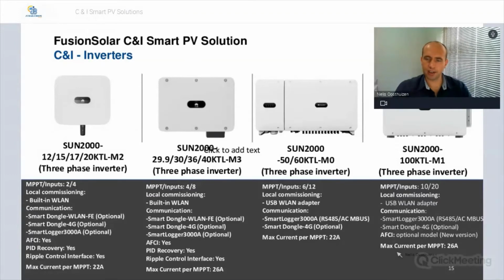And then note again that the maximum current per MPPT is 26 amps, which means it supports all the newer high-powered modules, which have a short-circuit current of about 13 amps.